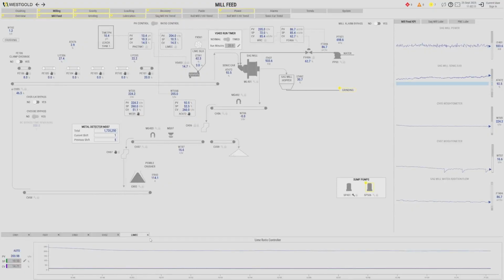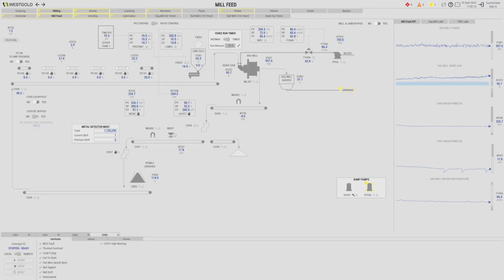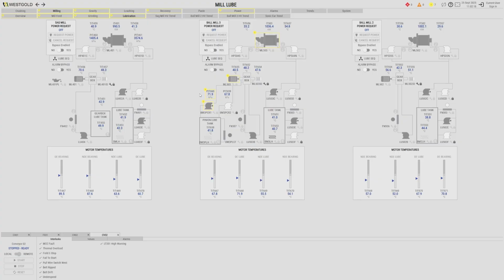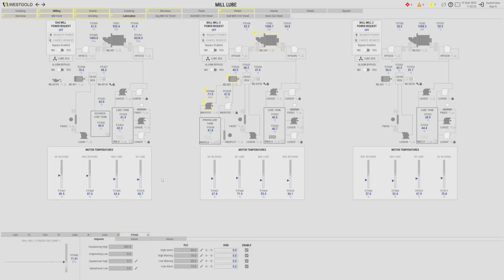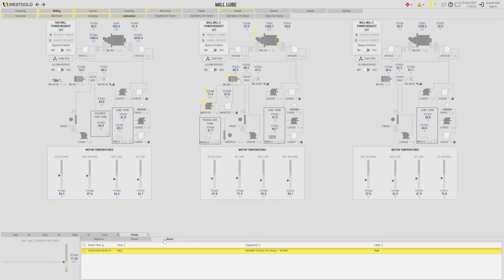We also created features to allow supervisors to change the minimum and maximum operating values of the analog equipment, with shading on the graphs to indicate the ideal process operating range. This way operators wouldn't have to guess how to run the plant, but could see optimal performance just by looking at the screens.